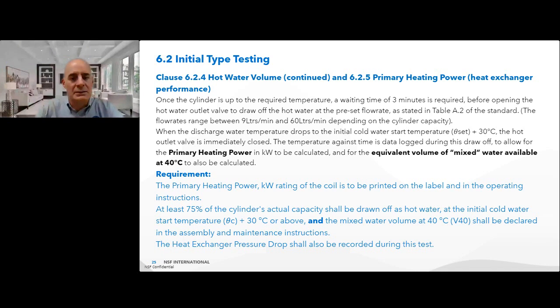The temperature against time is recorded to allow for the primary heating power in kilowatts to be calculated, and for the equivalent volume of the mixed water available at 40 degrees to also be calculated. The requirement of this test then is that the primary heating power, the kilowatt rating of the coil, is to be printed on the label and in the operating instructions.